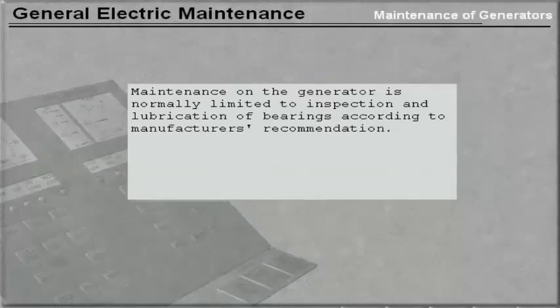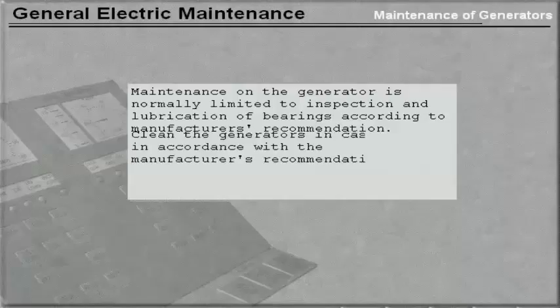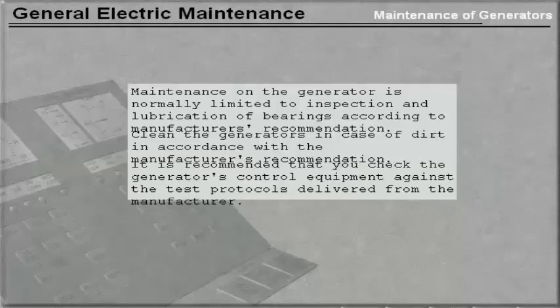Maintenance of the generator is normally limited to inspection and lubrication of bearings according to manufacturer's recommendation. Clean the generators, in case of dirt, in accordance with the manufacturer's recommendation. It is recommended that you check the generator's control equipment and compare them to the test protocols delivered from the manufacturer.